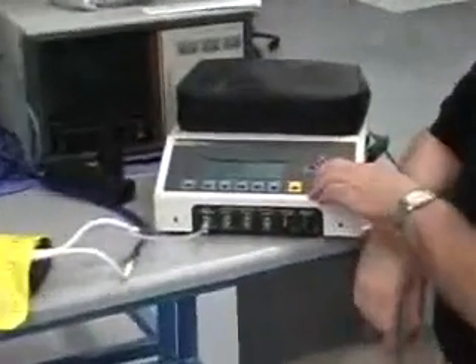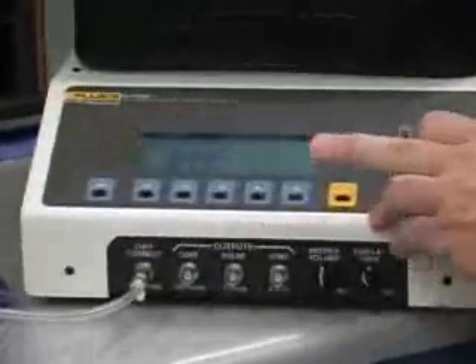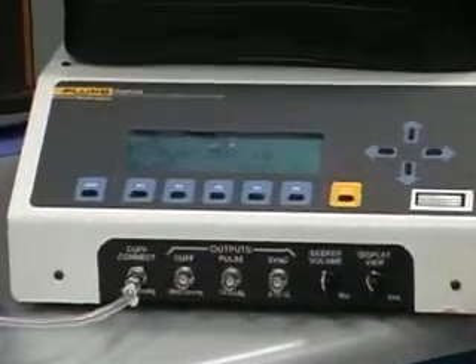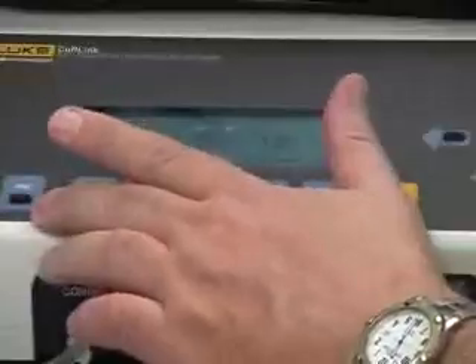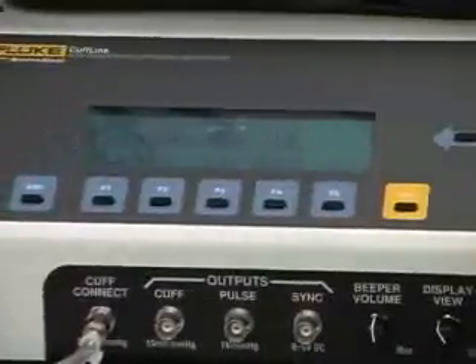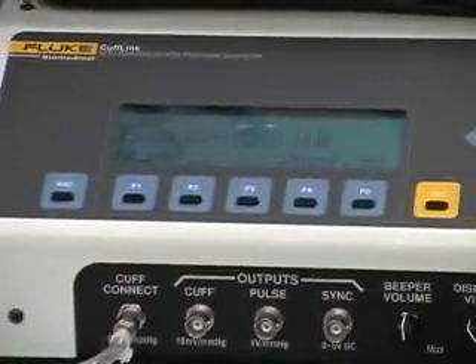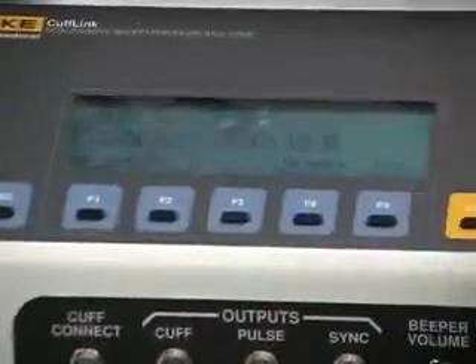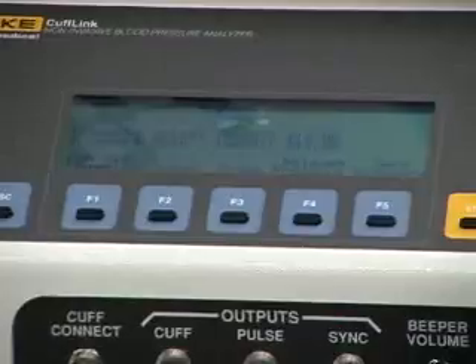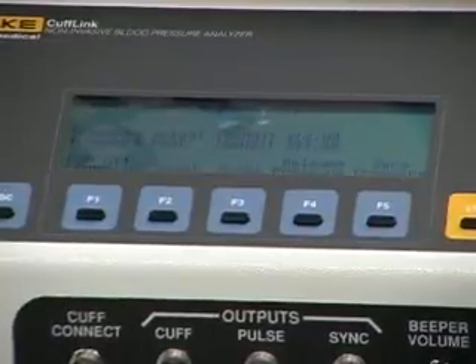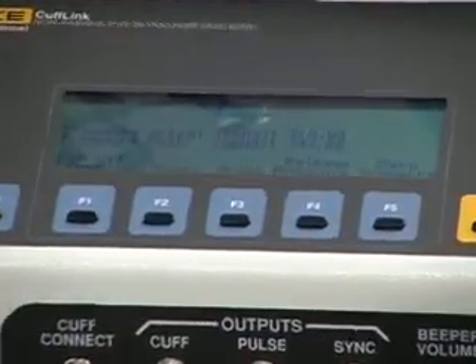Use the cursor again here to go down to pop-off. Hit enter. And now we just turn the pump on. And you can see the pressure is going up. At 250 it's going to begin flashing because that's the maximum pressure range. It's going to keep on going.